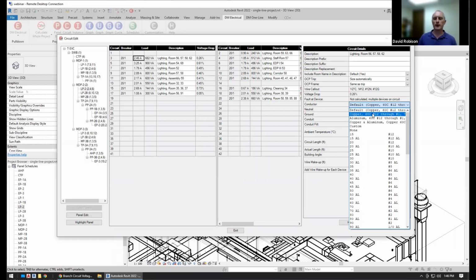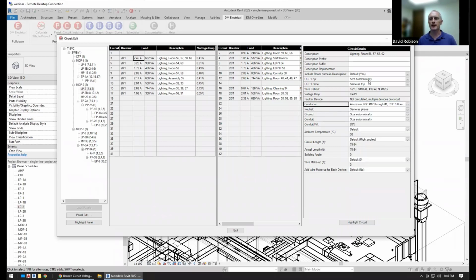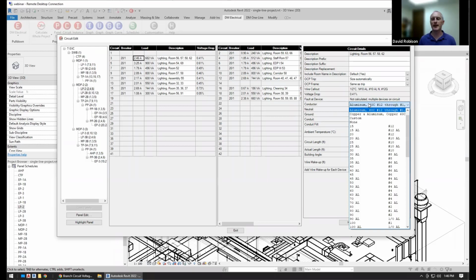You can also choose a specific wiring option. By default, it's choosing copper. We could force it to copper, which isn't going to change anything. We could also change it to aluminum. So if we select aluminum, it's now going to size it automatically based upon the trip, just using our aluminum wires rather than our copper wires. So you can switch back and forth. It's still sizing it automatically, just using a different criteria.